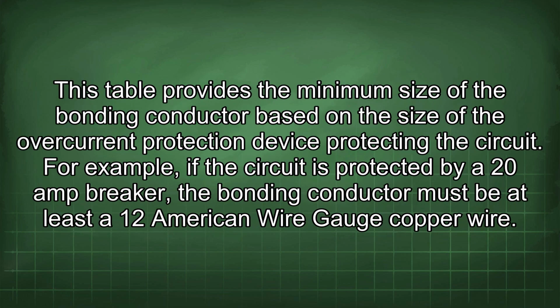This table provides the minimum size of the bonding conductor based on the size of the overcurrent protection device protecting the circuit. For example, if the circuit is protected by a 20-amp breaker, the bonding conductor must be at least a 12 American wire gauge copper wire.